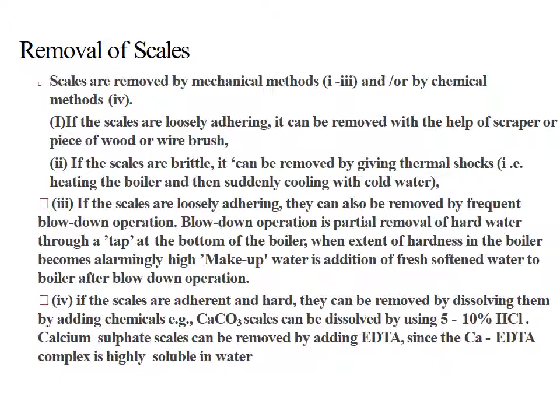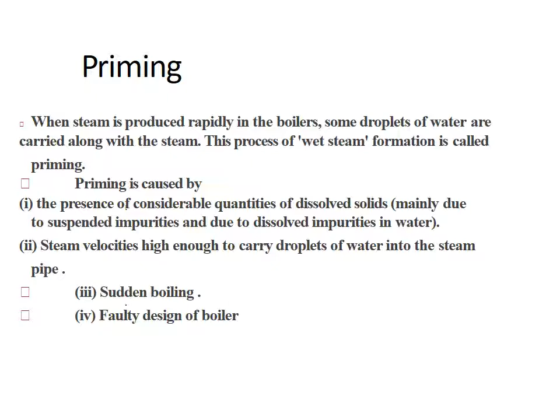Priming. When steam is produced rapidly in the boiler, some droplets of water are carried along with the steam. This process of wet steam formation is called priming. Priming is caused by: 1. The presence of considerable quantities of dissolved solids, mainly due to suspended impurities and dissolved impurities in water. 2. Steam velocities high enough to carry droplets of water into the steam pipe. Priming is also caused by sudden boiling, and by faulty design of the boiler.